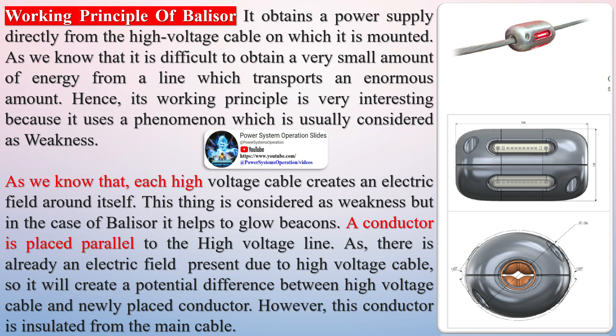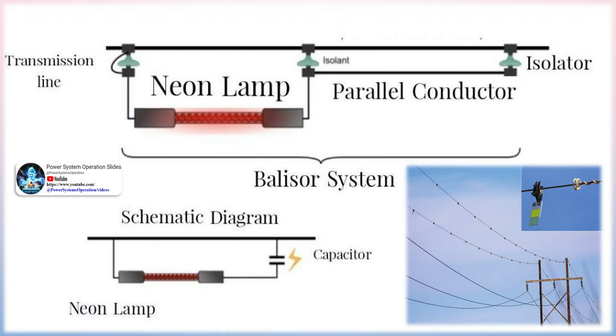Balisor is a system of illuminated beacons for high-voltage power lines using a cold-cathode low-pressure neon lamp, used as an aircraft warning light during nighttime. High-voltage lines represent a significant danger for aircraft flying at low altitude. The marking of the pylons is not sufficient to ensure the necessary safety given the very long spans. The Balisor system ensures the marking of high-voltage conductors by extracting the energy necessary for its operation from the line, and it is perfectly autonomous, guaranteeing a constant light intensity whatever the line current.